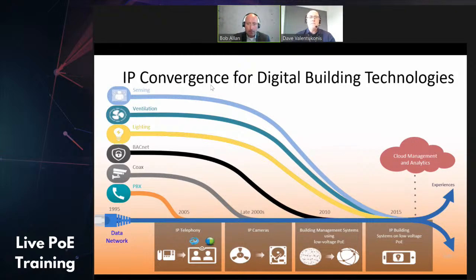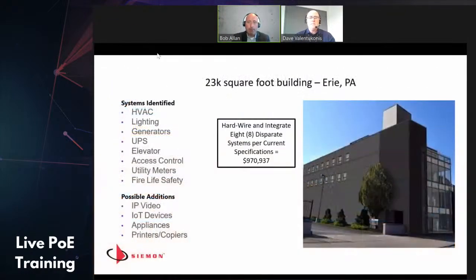We're also looking now at situations where being able to bring all of those systems down onto the network allows us to take great advantage of an integration platform. When we use an integration platform, we can typically save about $500,000 per 100,000 square feet of construction by eliminating things like proprietary software, making sure the end user, the owner of that building, isn't vendor locked for the life of that building, and giving us the option of taking advantage of the open market during the operations phase.